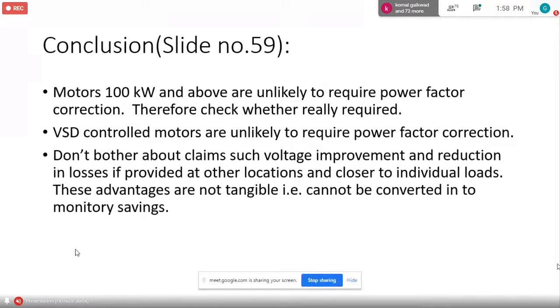Motors of 100 kilowatt and above are unlikely to require power factor correction. Therefore, check whether it is really required. VSD controlled motors are unlikely to require power factor correction because the VSD takes care of it. Don't bother about claims such as voltage improvement and reduction in losses if provided at other locations close to individual loads. These advantages are not tangible, that is, they cannot be converted into monetary savings.